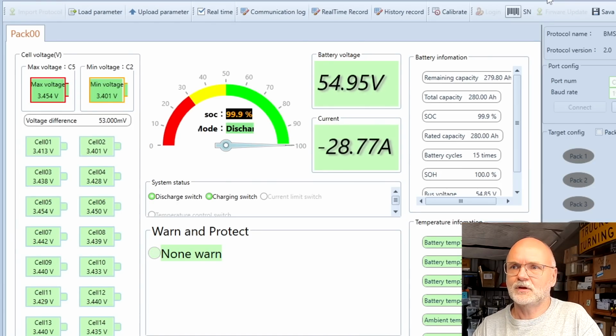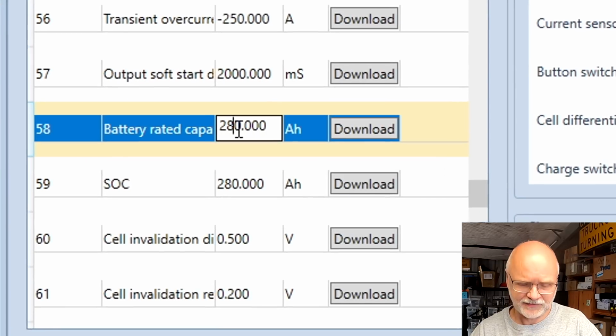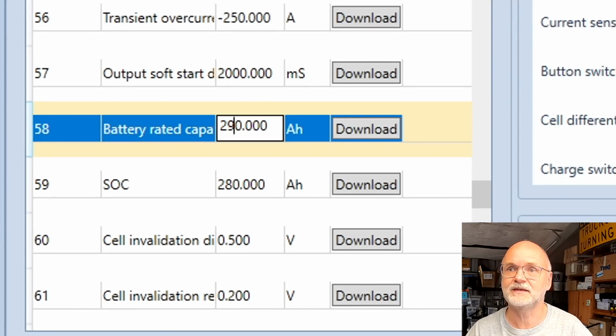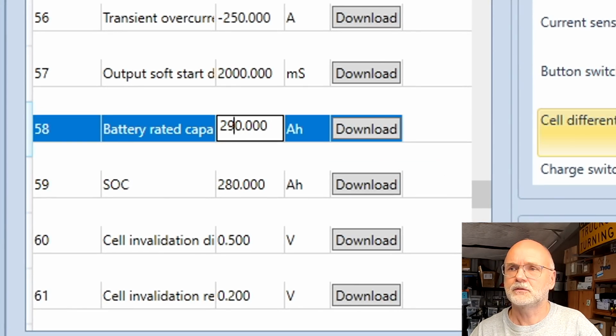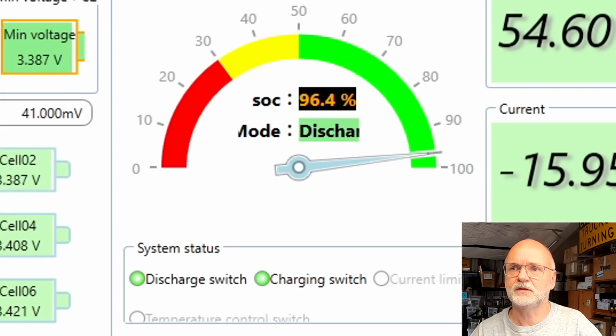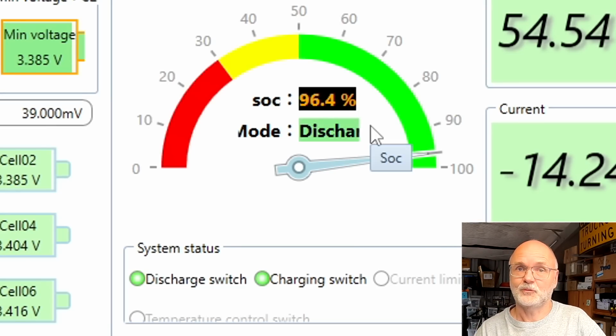Let's leave this running for a couple of minutes, then turn it off again and recharge the battery to 100%. I will also fake the rated capacity here, let's fake this one to 290 ampere hours, because this will now fake the state of charge. We are now down to 96.4% already. Once we recharge the battery, we will see if this resets to 100%.